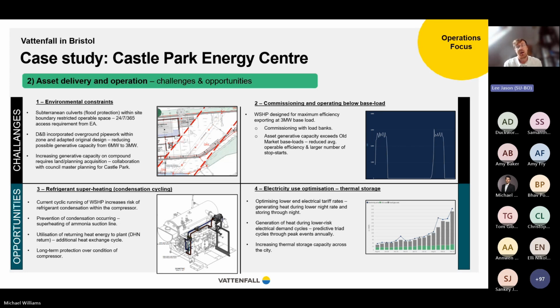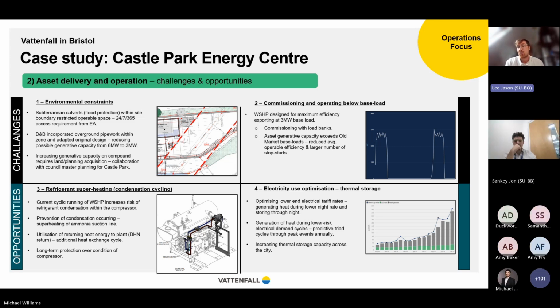Another challenge we had and we're having today is around the commissioning and operating below the base load of the asset. So the asset being a 3 megawatt asset, originally when we were commissioning, we were around 1.5, so around half that load. So it did have that requirement of load banks and all the space that would entail, as well as operating with a peak around 2.2 to 2.4 right now. It does mean we see a reduced average operable efficiency. So our co-efficiency is a little bit lower than we would like, or the average. And then obviously, more importantly, a large number of stop-starts, which compressors of this size don't necessarily want over a long period of time. So that's a challenge of increasing capacity and demand on the network, or interconnections of our other island networks, which we have within Bristol.